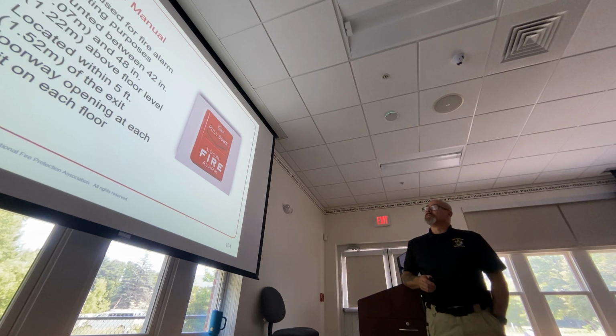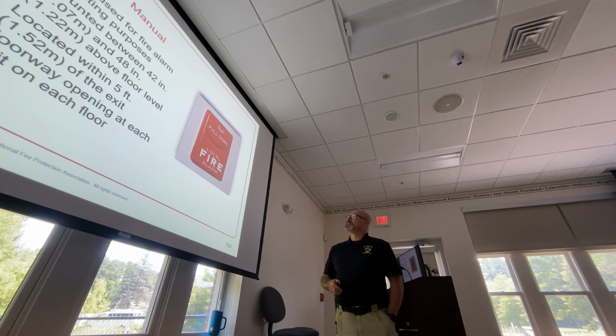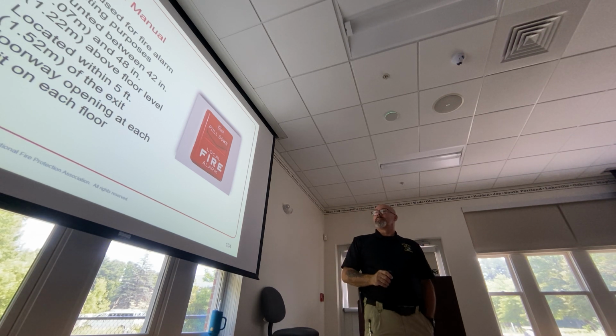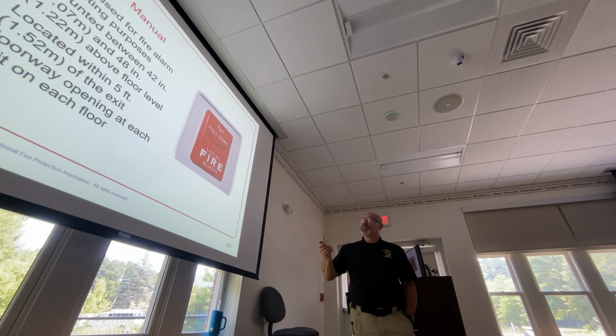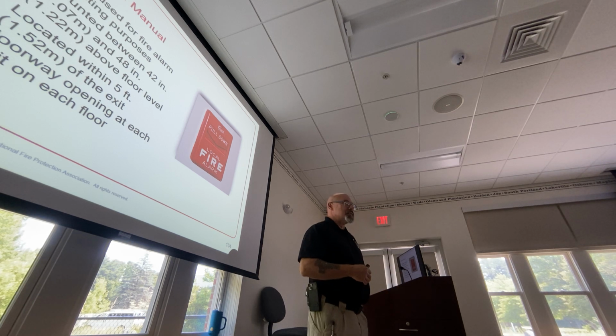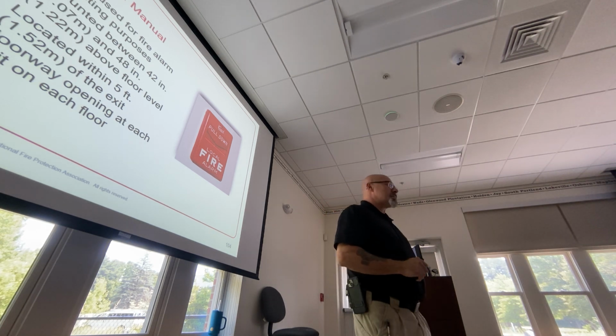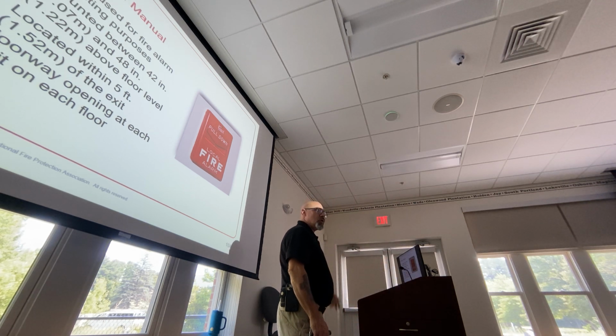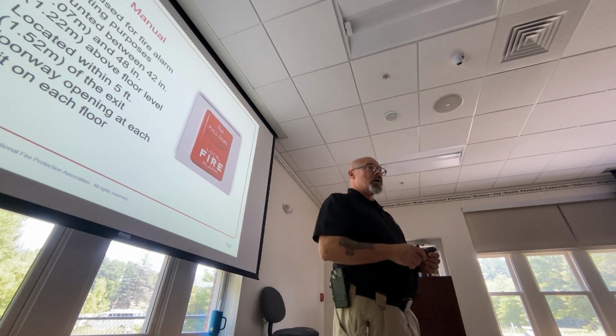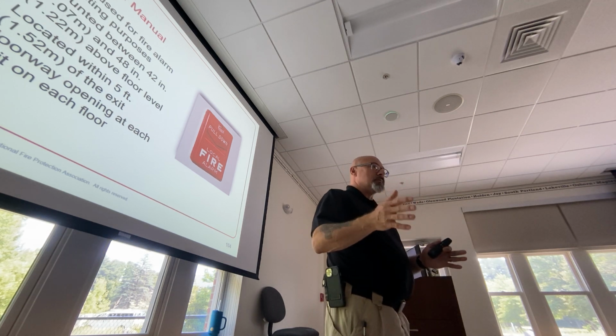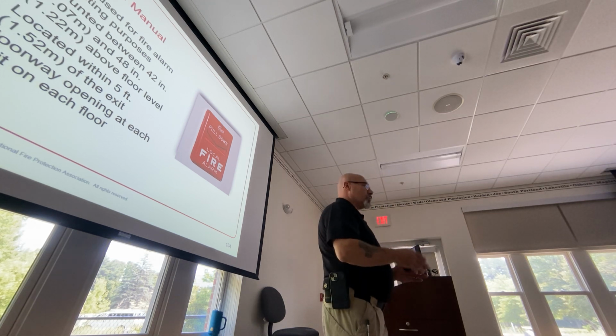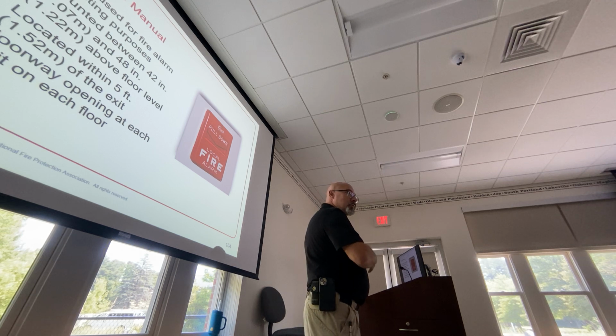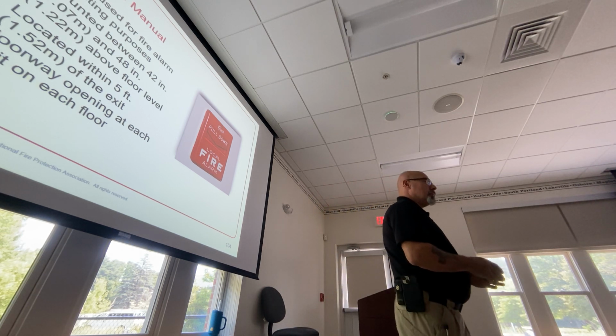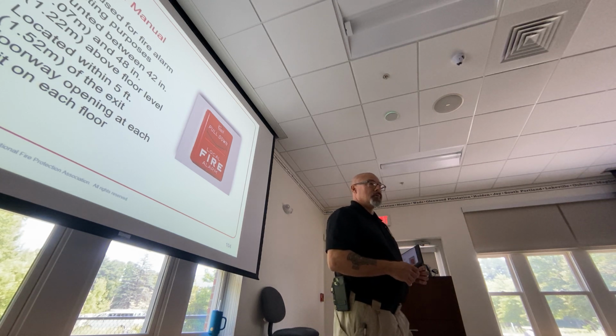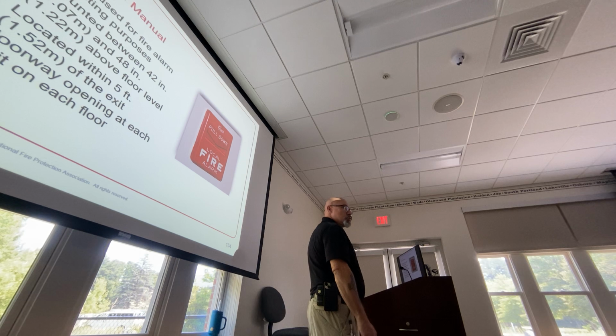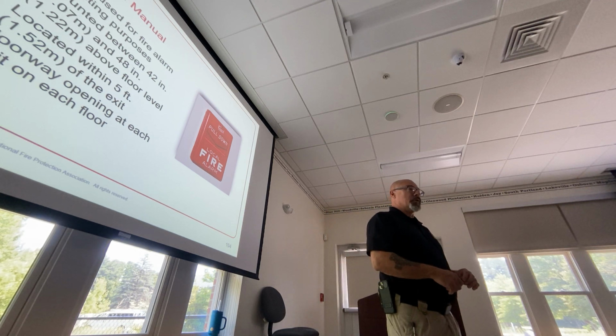So manual pull stations are only used for fire alarm initiating purposes. Hold down to alert. They have to be mounted between 42 and 48 inches above the floor level. Here's a big debate that we've had in the past: as an inspector, if I find that it's not installed correctly, that is not a deficiency during an inspection. It's existing. If it's brand new, you call out that the installation was incorrect. But as an inspector, I just need to make sure that I have a manual initiating device in place and that it's functional.